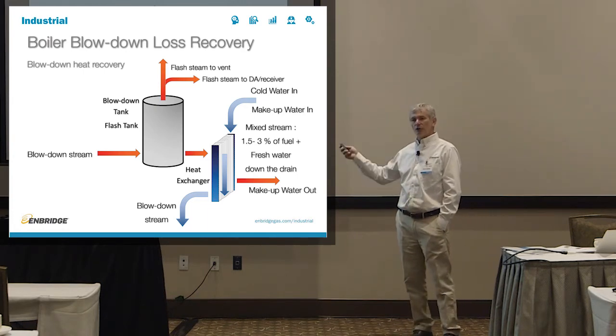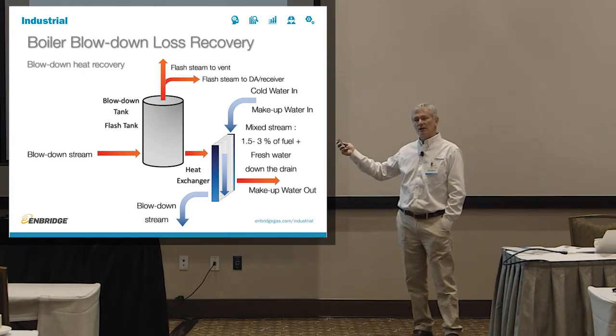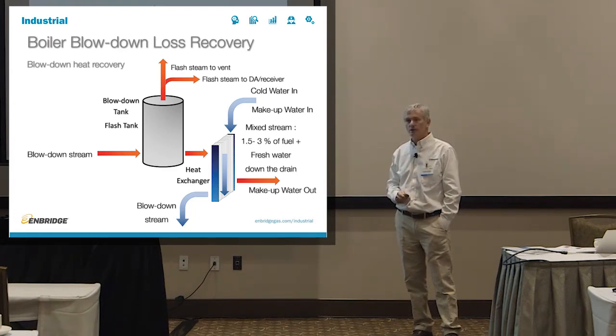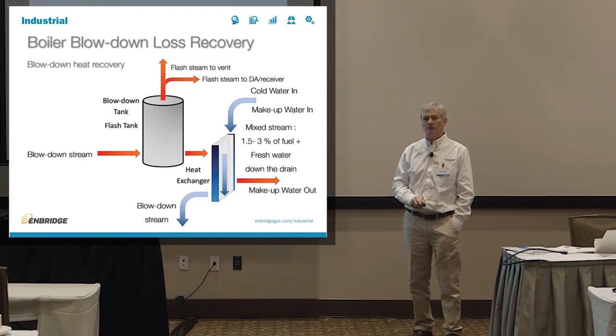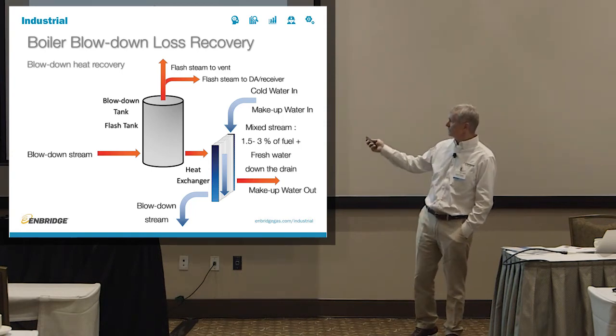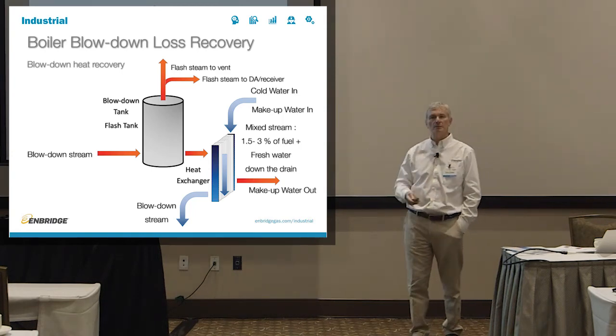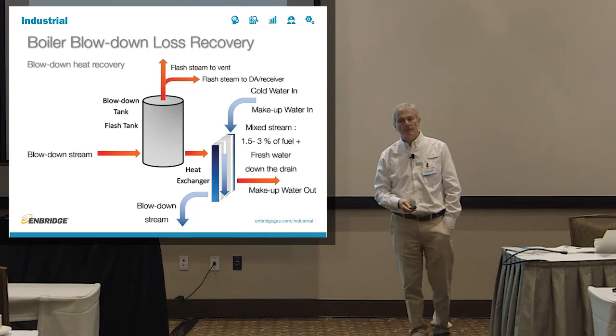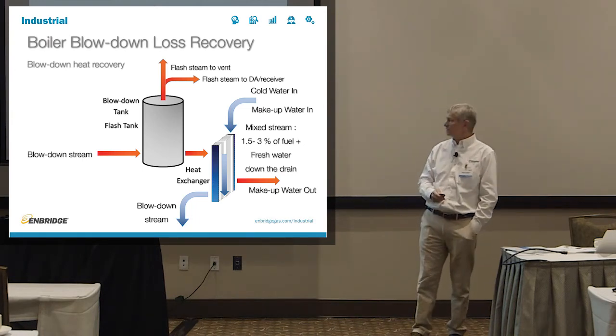It would be much better if you can put in a heat exchanger. So when you release that blowdown stream, instead of mixing it with the cold water, it goes through the heat exchanger. It still gets released into the drain after that, but by now the energy out of it has been used to preheat the makeup water. That's a good first step.